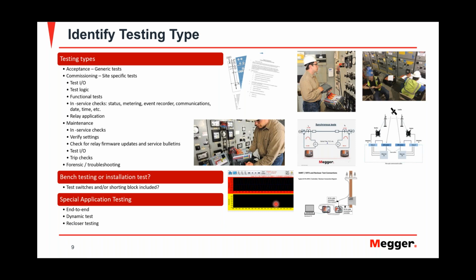Another test that you could do is recloser testing, and the quirkiness on this one is depending on the relay test set that you use, you may need a separate box or a separate interface between the relay test set and the recloser controller. So that's another thing that you have to keep in your head. If you're, let's say, testing a recloser, what interface or what other accessories do I need for my relay test set?